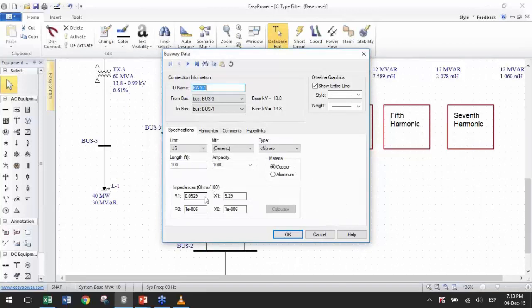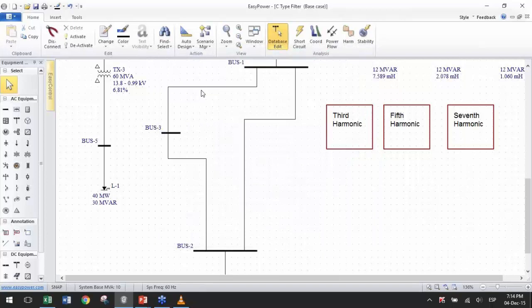In here, this is my inductance, and there we have the positive sequence reactance is 5.29 ohms per 100 feet. So to have this in ohms, I'm going to enter 100 feet. Now, every inductor should have a little resistance. And I'm considering this is a very high quality inductor which has an X over R ratio of 100. So the resistance, the positive sequence resistance, is 100 times lower. It will have some losses as any real inductor, but these are low. This is very high quality. And for the zero sequence resistance and reactance, I'm going to use the smallest possible value that I can input in EasyPower because I don't want to consider those, not for now. This is the inductive part.